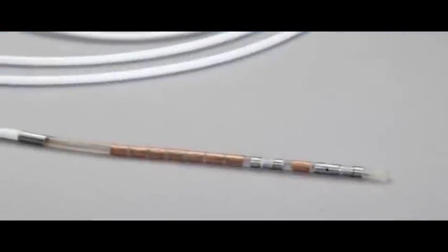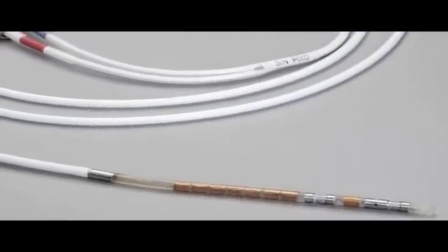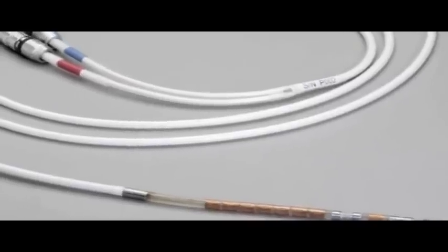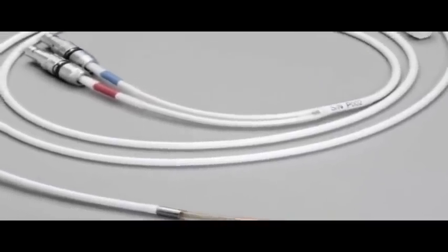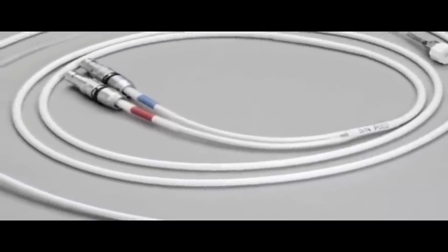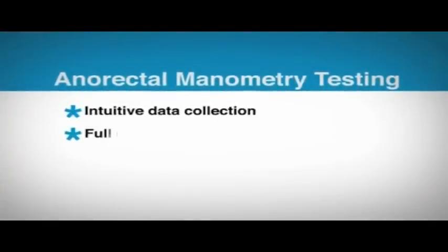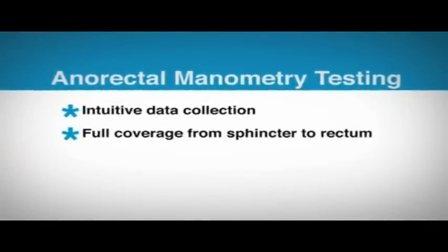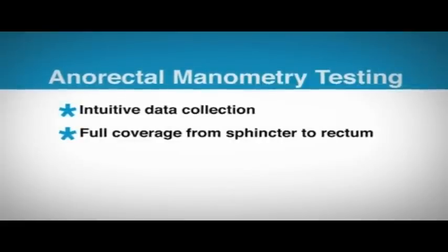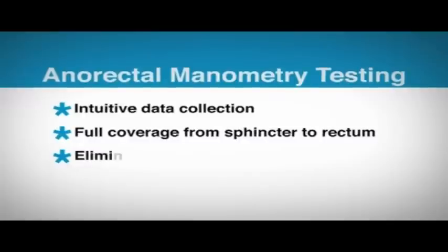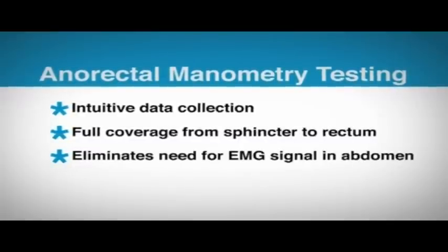The ManoScan high-resolution tactile technology also provides for simple and efficient anorectal manometry testing. With many of the same features and benefits as the ManoScan esophageal software, the ManoScan anorectal software allows for similarly intuitive data collection. The probe's continuous sensing provides full coverage from the sphincter to the rectum, eliminating the need for repositioning. These balloon sensors in the rectum also do away with the need for an EMG signal in the abdomen.